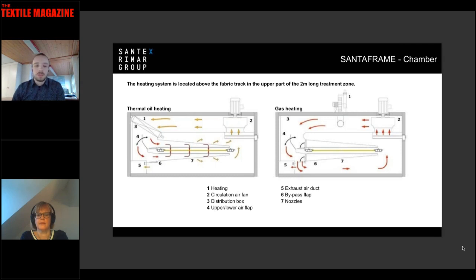With semi-indirect gas heating, the flames are located in a combustion chamber. Hot air is introduced to the circulating air via a large perforated distribution pipe, which ensures a very even temperature distribution. Conventional systems heat the recirculating air over the open flame of the gas burner.